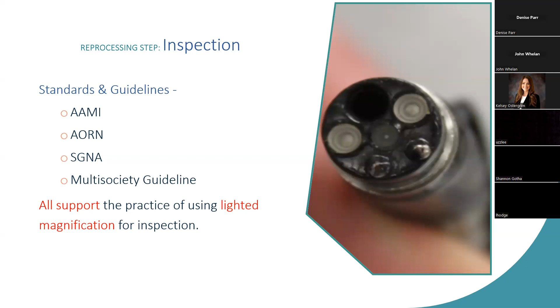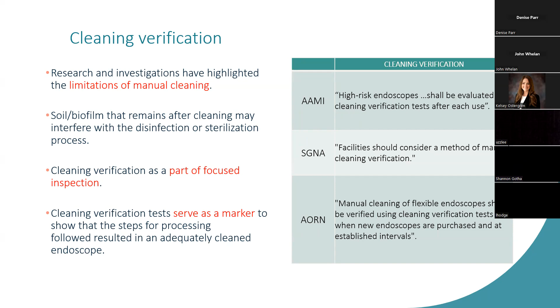As we stated, any soil and/or biofilm that remains can interfere with disinfection or sterilization. So cleaning verification needs to be part of focused inspection. And cleaning verification, as the title implies, has to happen following cleaning and before disinfection or sterilization. You do not perform cleaning verification at the very end of the process. As you see on the screen here, the predominant standards in professional organizations speak to the need to incorporate such quality control. AAMI and AORN point out that high-risk endoscopes should have it performed every time. For non-high-risk endoscopes, the facility determines the frequency based on a risk assessment.